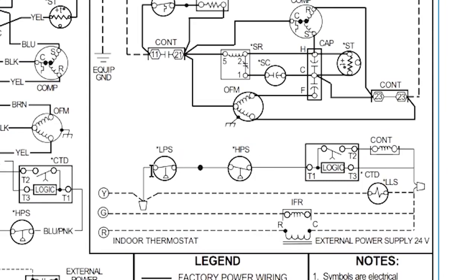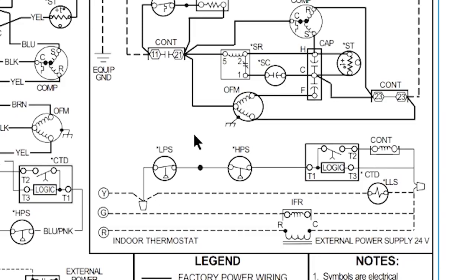Now for the pressure switches: when pressure increases, this one opens — it's normally closed. However, the factory actually labeled the diagram incorrectly, swapping the LPS and HPS labels. A low pressure switch should open when pressure falls and close when pressure rises. A high pressure switch should open when pressure rises. These two are switched on this diagram — just a little typo that often doesn't get caught for years because people aren't looking carefully at the actual diagram.